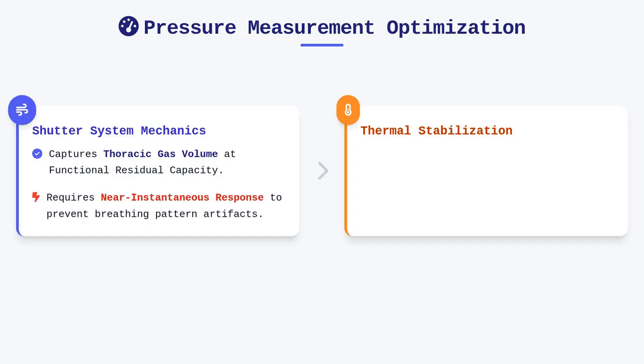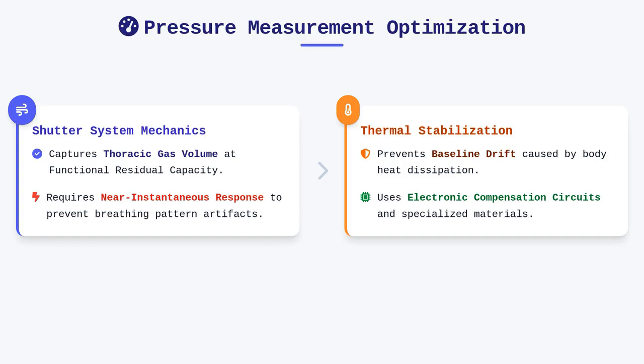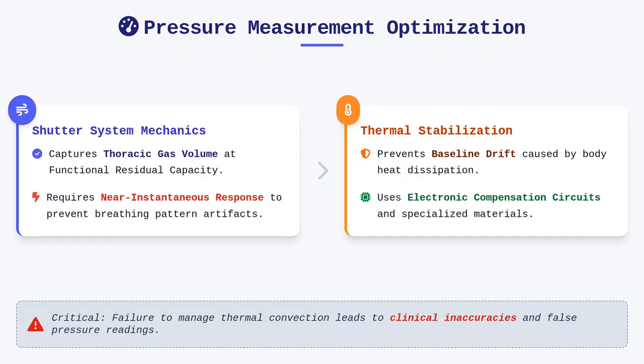Furthermore, we must address the thermal stabilization of the air inside the box, because heat dissipation from the patient's body can introduce significant baseline drift. We achieve this stability through deliberate material selection and sophisticated electronic compensation circuits that neutralize the signal baseline. Without this thermal management, the pressure transducer would respond to convection currents rather than genuine thoracic volume changes, leading to clinical inaccuracies.